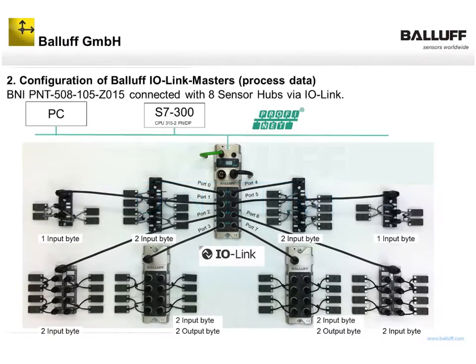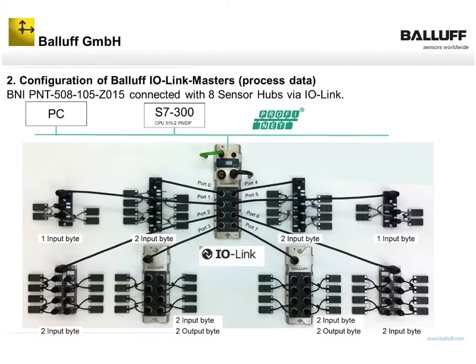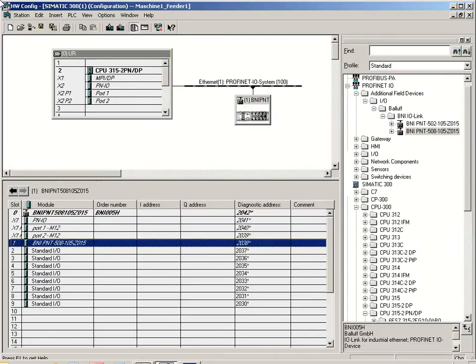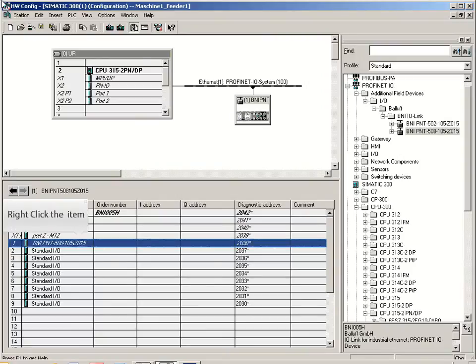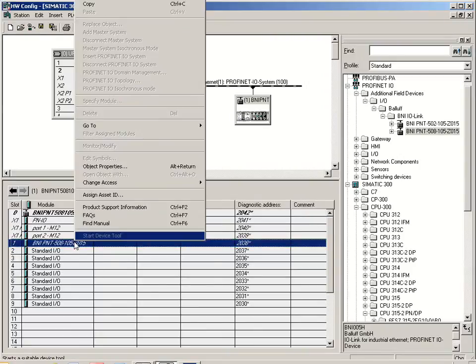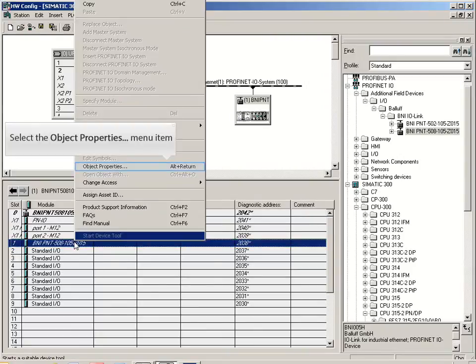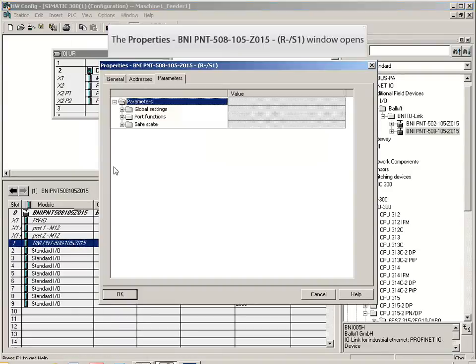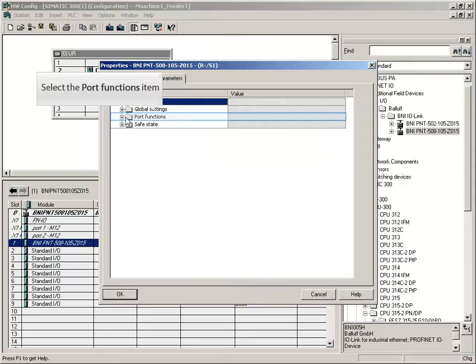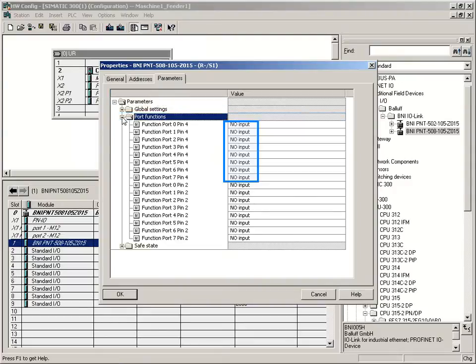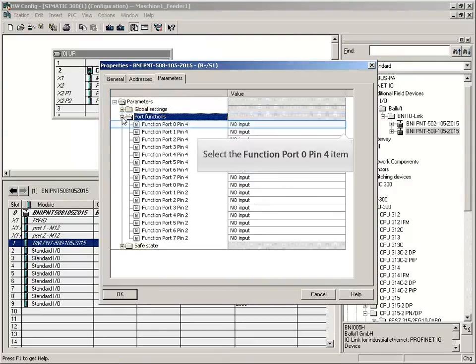The process data of the IO link devices will be configured as shown with the tool hardware configuration of Siemens. All ports of the IO link master shall be run in IO link communication mode. For this purpose, open the object properties, select the port functionality. The default setting of the ports is no input. We change this into IO link.